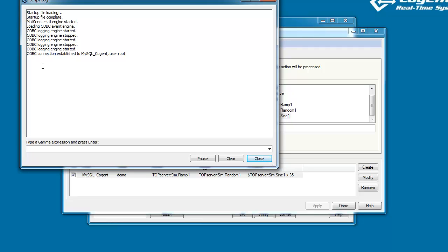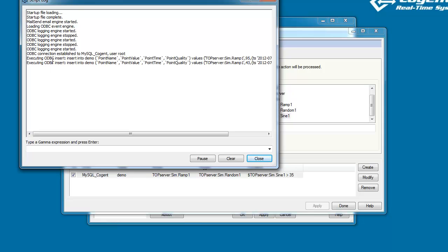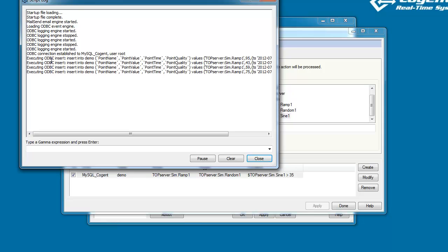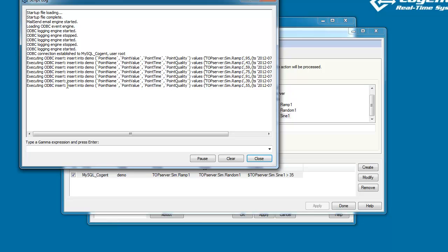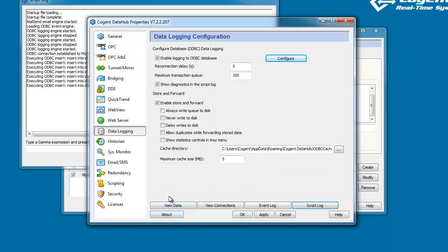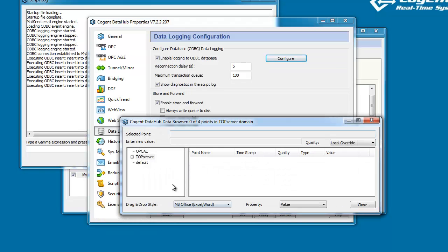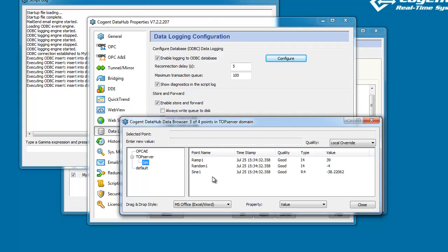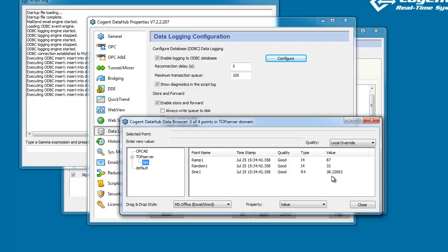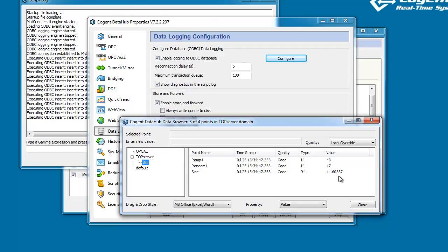And right away, if we watch here, we should see some values being written to the database table. And there we are, we're seeing several insert commands. If I come back and show you the data values again, you'll notice that when Sine1 is less than 35, it doesn't matter how many times Ramp1 is changing, data will only get written when Sine1 is above 35. And there we go. So that shows our trigger condition being evaluated.